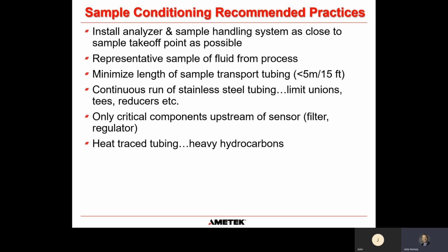One is you always want to have your analyzer and your sample handling system as close as you can to each other in terms of the sample takeoff point. You don't want to install an analyzer and a sample conditioning system hundreds of feet or miles away from where you're taking off your sample point. Minimum, if you can, less than 5 meters or 15 feet would be sort of ideal. So try to do that and think about that as you're designing where you might want to put your analyzer relative to where your takeoff point is for your process.